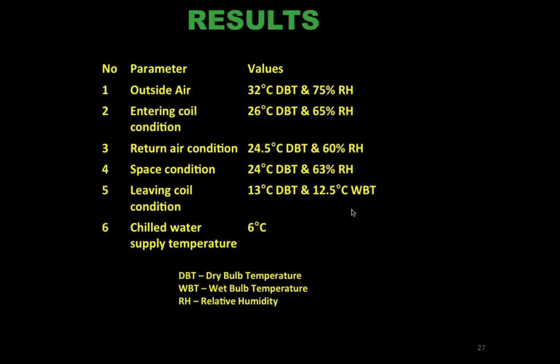Even if we had sized the coil correctly at installation and commissioning, the loads change through the day, through the various months, and through the year, because it's bound to happen. Cooling loads in the space are never constant, so we will have several hours of part load operation. The coil is oversized for such a condition. It is inevitable that loads are going to be different. What we design and what we install, the nature of operation is such that we need to go through a peak load and a whole series of part load conditions.